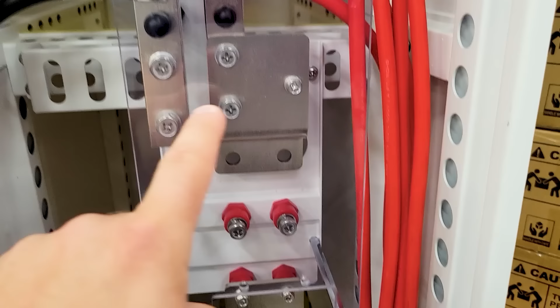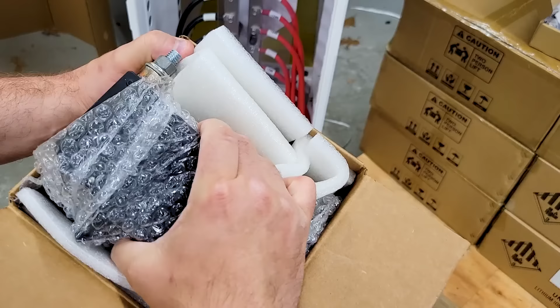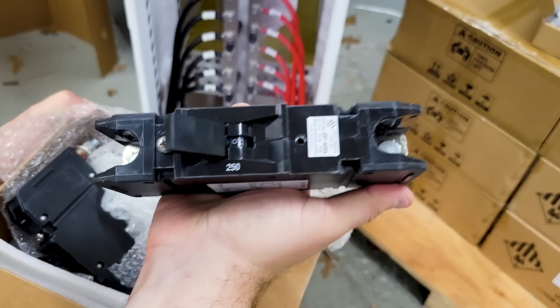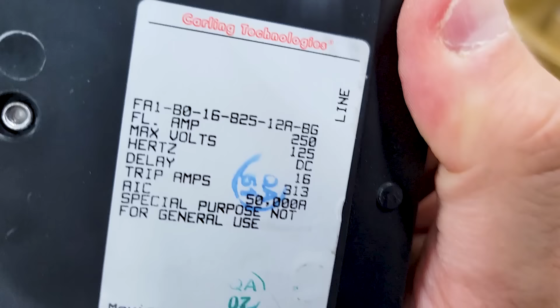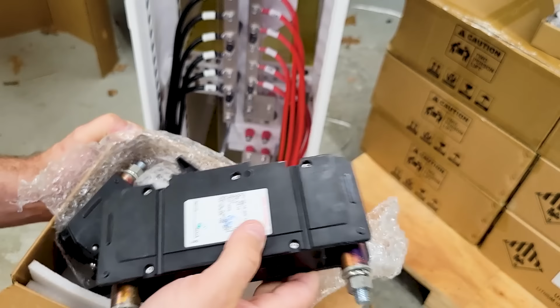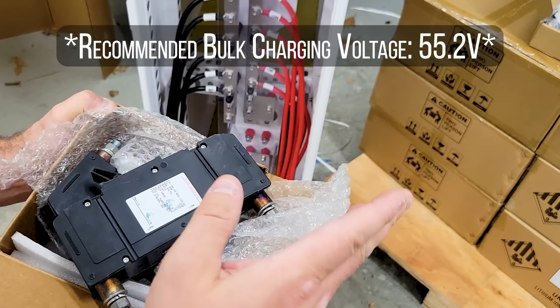Something down here in the bottom, I'll pull that out and check it out. Looks like we have some communication wires as well as these steel feet that'll let you bolt it to the floor if you need to. This cardboard box was on the pallet but not inside the cabinet, so this might be a separate part number. And let's open it up. Should be the circuit breaker. 2 circuit breakers. Okay. All right, so these are 250 amp circuit breakers. It says here 250 amp circuit breaker, 125 volts DC, which is plenty because maximum charging voltage on the batteries is 58.4 volts. So we've got more than a 2 times safety factor on this.